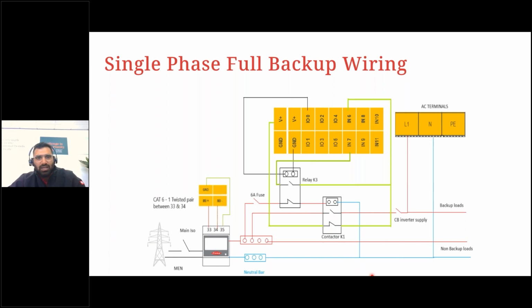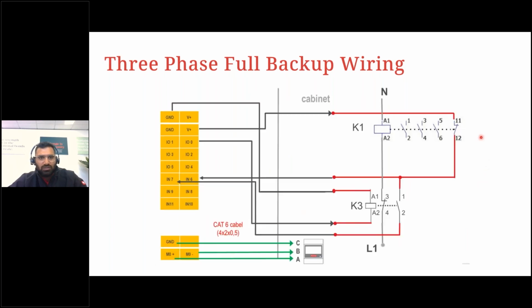So very simple. Whether you have a single phase or 3-phase, the idea is exactly the same. If you have a 3-phase, you just have to break 3 phases, but everything else is exactly the same. So if you look at this, exact same connections, IN6 is feedback from the contactor, IN7 is feedback from the relay, and we're just breaking 3 of the phases. And we have here ground and IO0 connected to the power supply of the relay. And we have just a V+ connection going. So pretty much this V+ needs to go through the contactor and relay and come back at IN6 and IN7 for the system to go into backup.